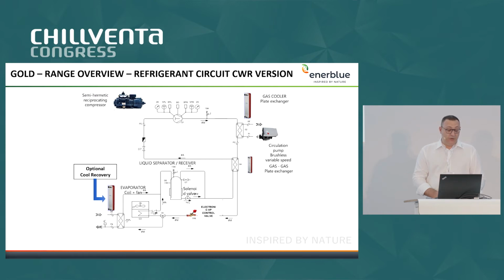We spoke before about the cold recovery option. You can easily see, compared to the air-to-water unit, we have an additional heat exchanger in parallel with the coil on the source side. And we can decide, using an external input, to use this exchanger to cool down the unit for the system. So also in this case, the circuit is extremely simple, and also the components are very, very simple. But in this case, we can use the unit to produce simultaneously hot water for domestic hot water purposes, for example, and cold water for the space cooling.